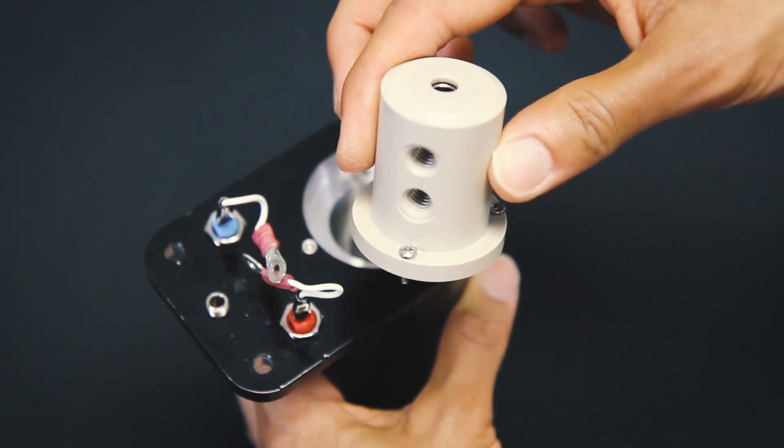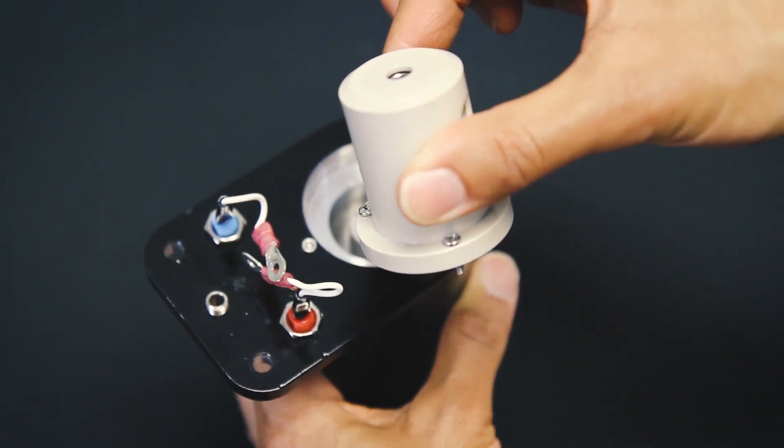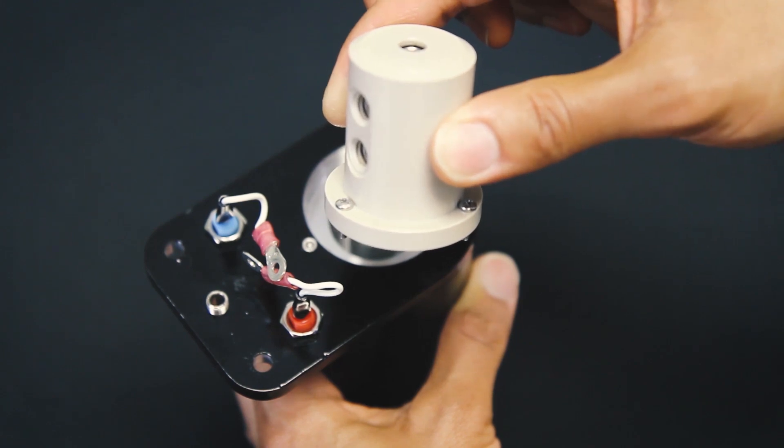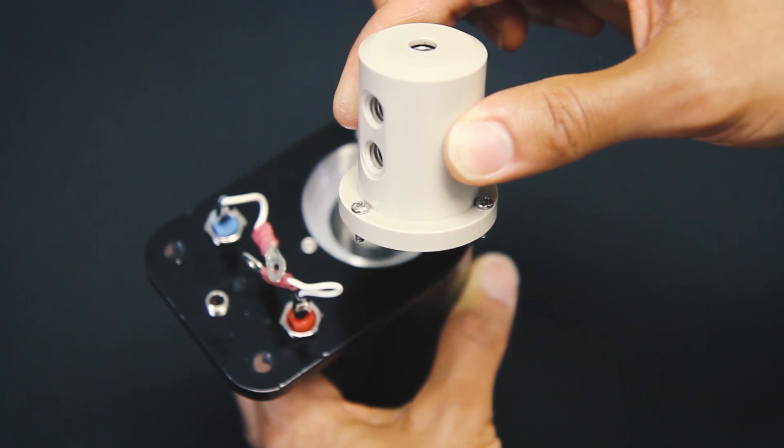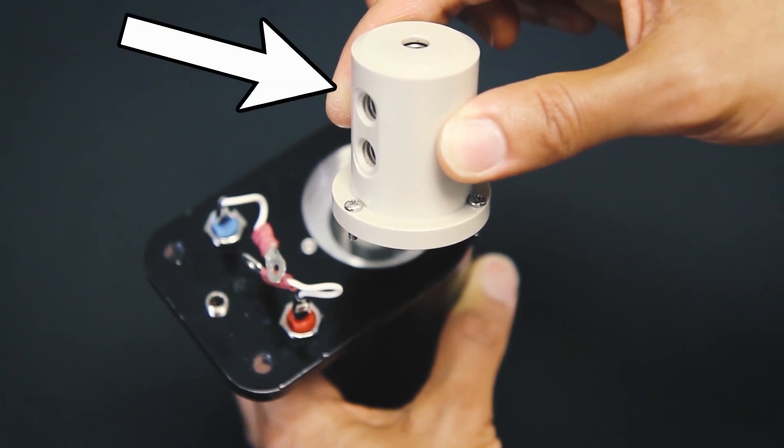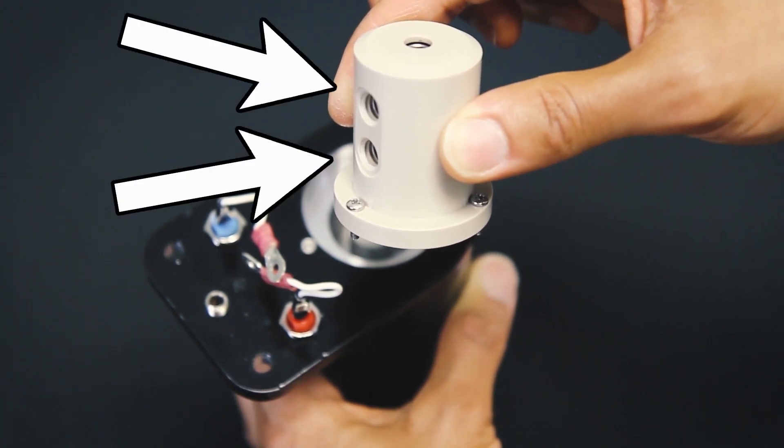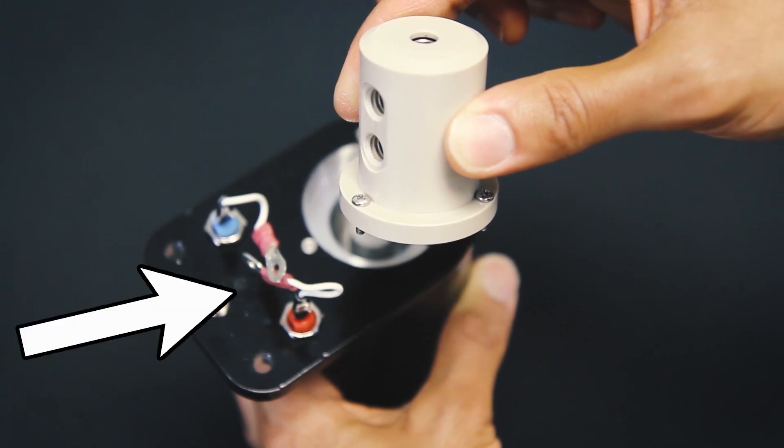Now replace the bearing assembly or clean out any silver graphite dust that might have accumulated in the bearing assembly. There are two holes on the bearing assembly where you mount the brushes. Make sure the holes are facing the disc and ring wires on the motor head bracket.